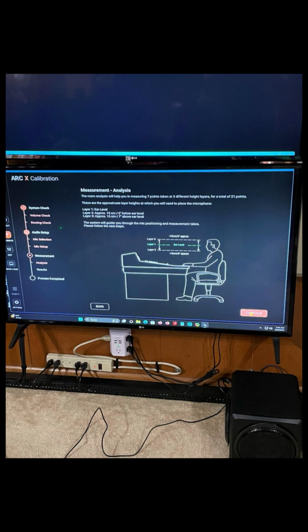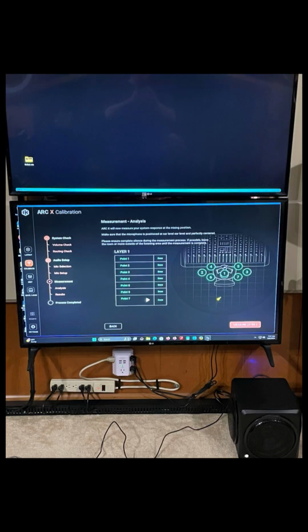There's ear level, 6 inches below ear level, and 6 inches above. This is just a picture of ARC-X software demonstrating the 3 layers. Here's an actual picture of ARC-X software with, on the far right, the 7 different positions, which I touched on in part 2. In the middle is the calibration. You select position 1, let it do the 3 sweeps. It gives you a pass or fail. Then you select position 2, and you work your way through the 7 different calibrations for each layer.